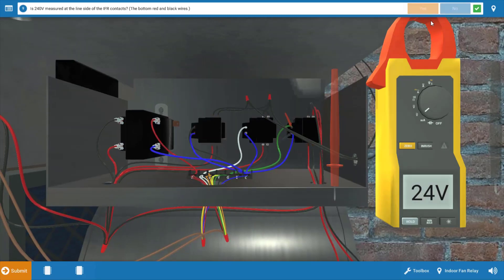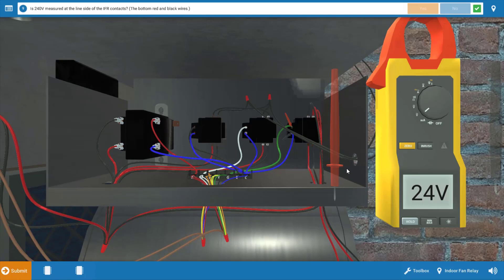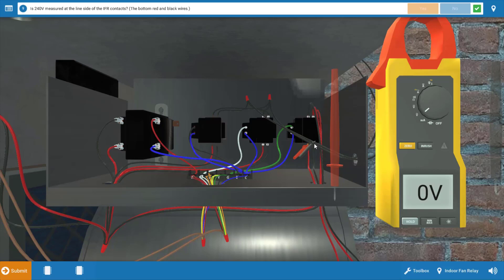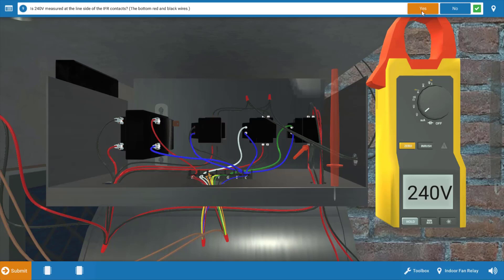Our next step is to verify that we have line voltage coming into the fan relay. It's possible that we have a loose connection somewhere in a wire nut, so that's what this will verify. Again, we're going to place our meter leads at the two glowing orange hotspots at the line side of the fan relay. When we do this, we have 240 volts. So we do have 240 volts coming to the fan relay, and we have 24 volts to the coil. We're going to click yes on the procedure guide.